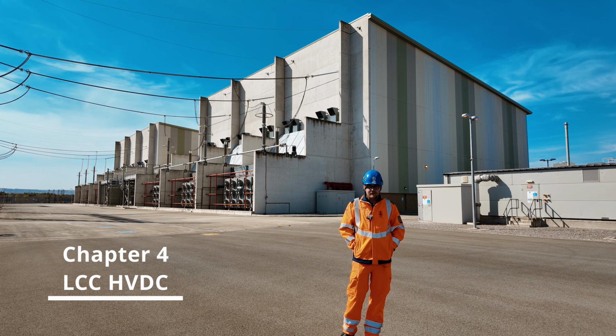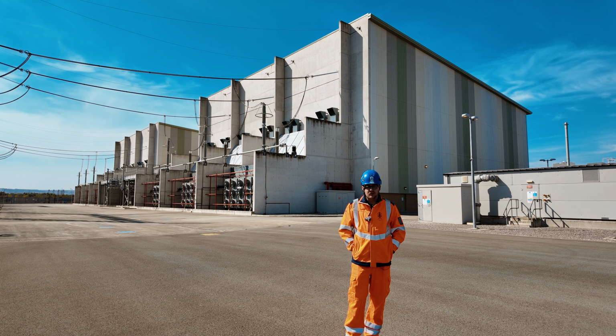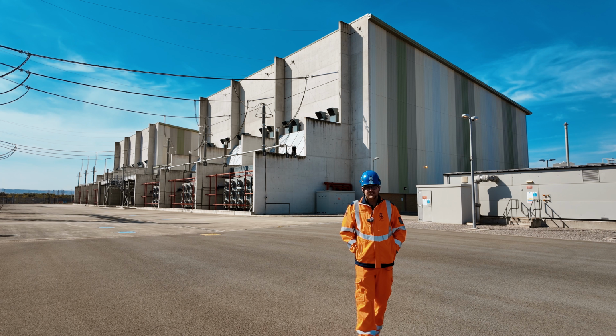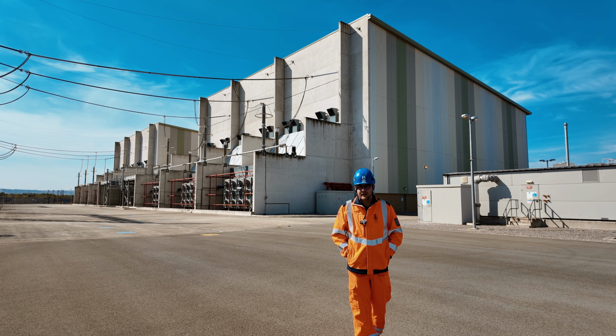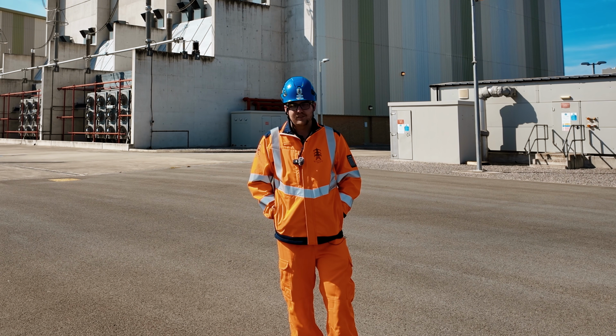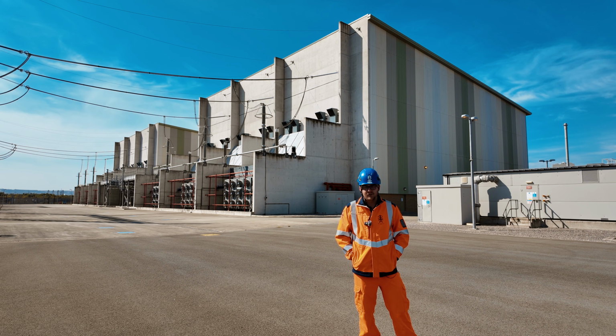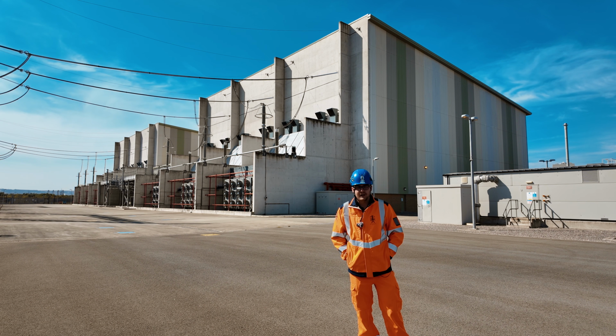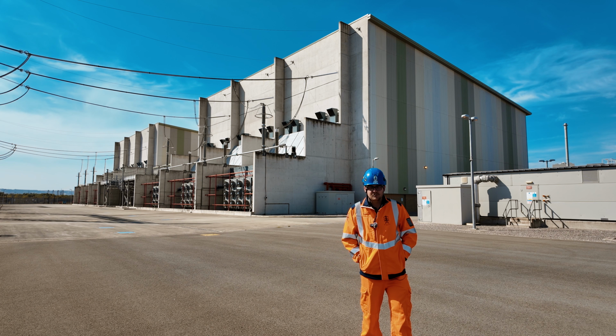I already talked about the fact that LCC, or line commutation converter, HVDC, like this, produces more harmonics than VSC, which is the alternative technology, which is why it needs so many filters. But another quirk of LCC, for it to work, it actually consumes reactive power, which is why it's not suitable for connecting to weak AC grids.